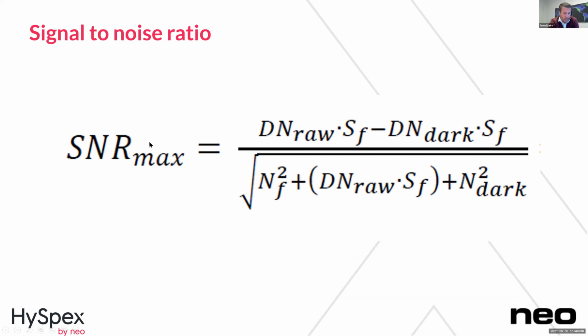Yeah, here you have the specification of signal to noise ratio in a hyperspectral system. The DN raw here, that's your raw data in digital numbers from your camera. Here you have photoelectrons per the DN level at saturation. So if you have a 16-bit detector, that's 65,535. So the signal here is then your raw data minus your dark current, part of your data, right? Then you have the noise contribution, which is your noise floor or the readout noise. So we usually characterize that with putting the lowest possible exposure time, no light to the system, then you can characterize the noise floor of your system. Then you have the photon noise on top of your signal and the dark current noise, because you're always subtracting a dark current, but that is usually quite much lower because you have averaged a lot of frames. I will come back to that.